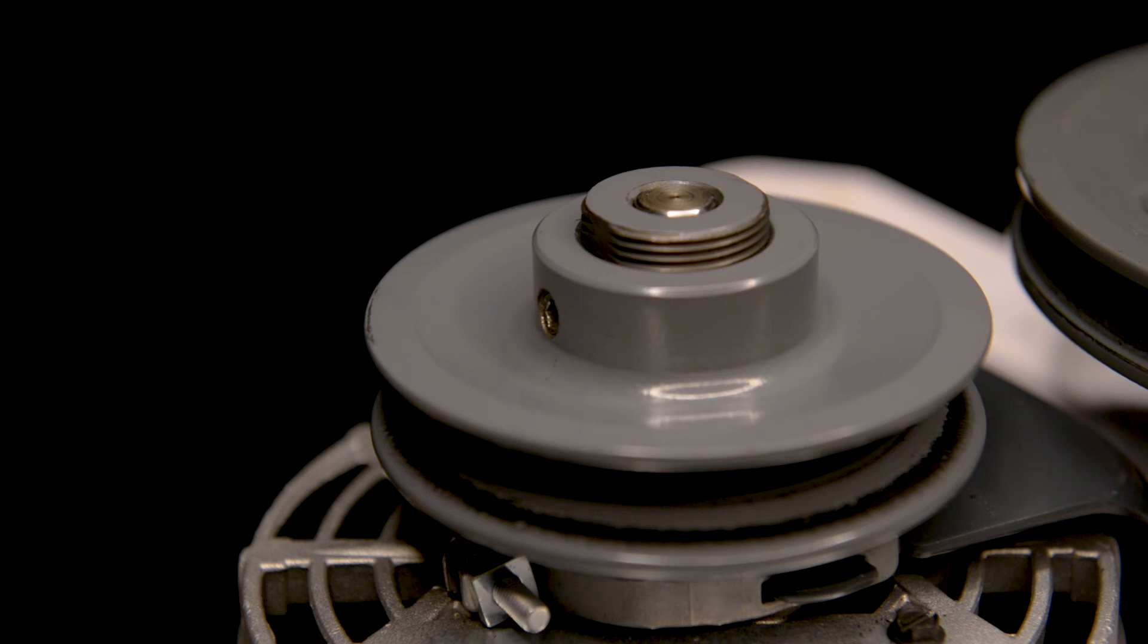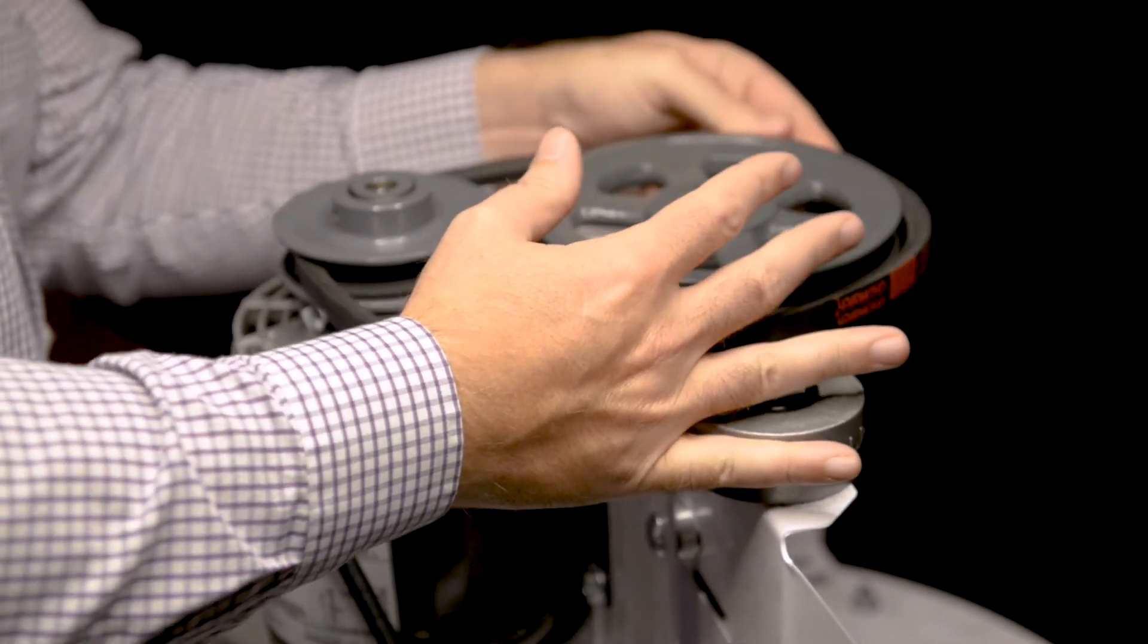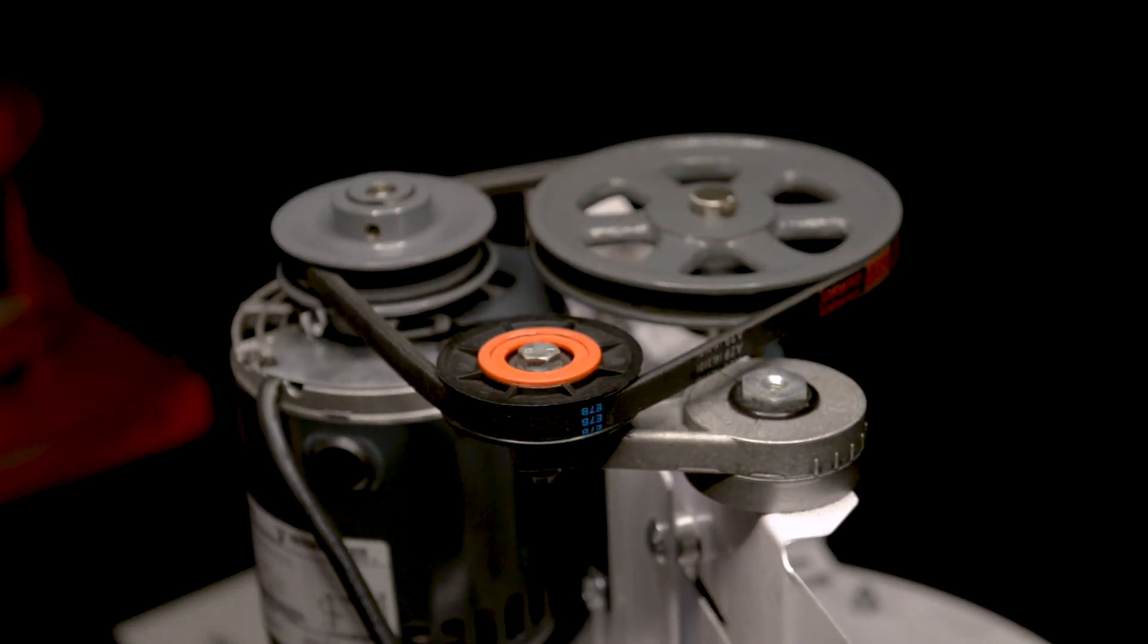Once this is completed, reinstall the belt. First position the belt on the belt tensioner, apply pressure to the tensioner, and slip the belt over the fan and motor pulleys. Before running the unit we must check belt alignment.